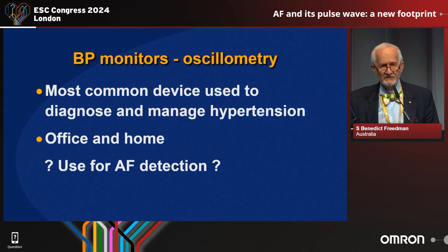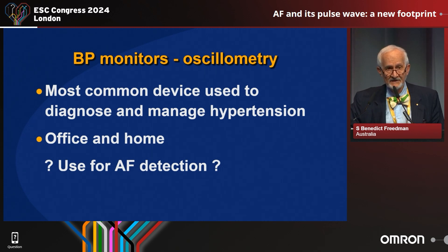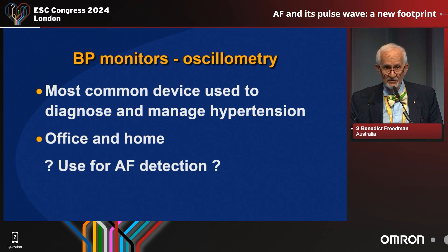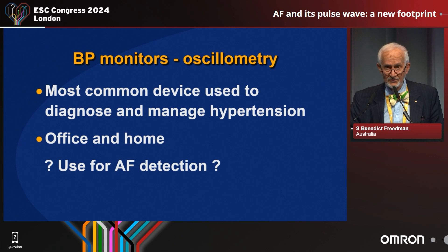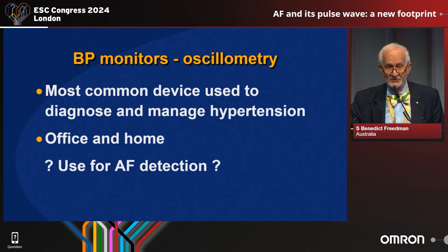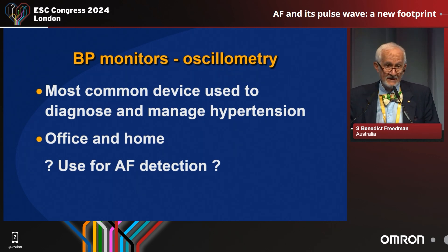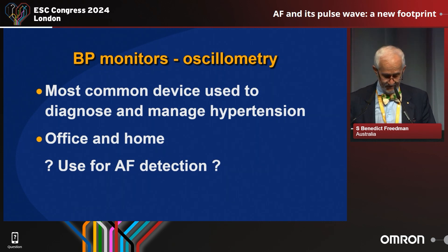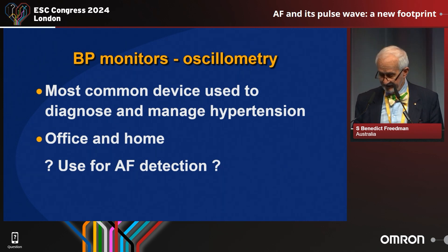As far as checking for blood pressure elevation and measuring the blood pressure, the most common type used around the world is oscillometry — it's a cuff. It goes around; you don't use a Korotkoff sound, you don't use a stethoscope. This is used everywhere in the world to diagnose and manage hypertension. It can be used both in the office and the home, and it can be used for AF detection, and that's what I'd like to speak to you about.